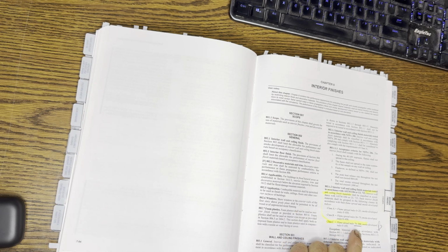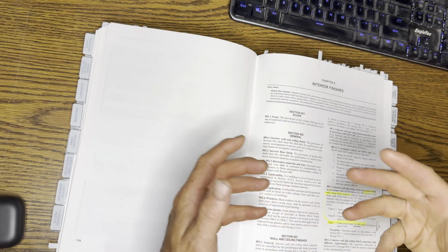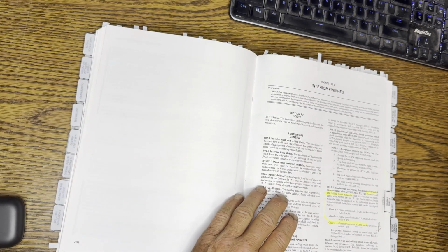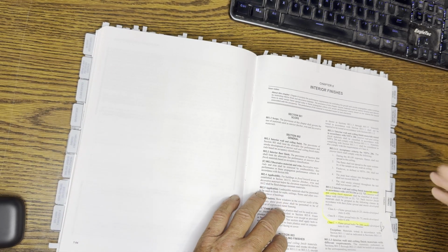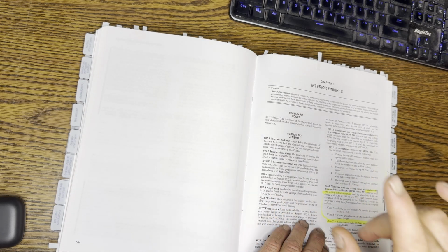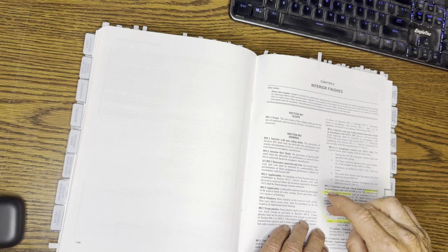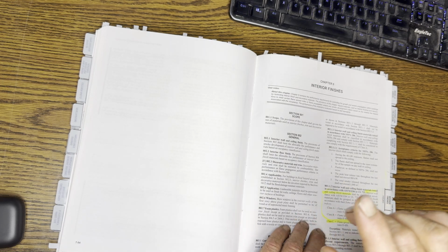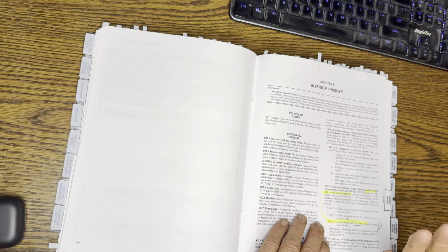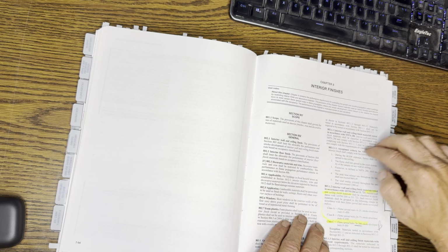And let me explain how this works for ASTM E84. It's the Steiner tunnel test, and what they have is this tunnel, and then they fasten the material on the roof of this tunnel. I don't know how wide it is. It's like 20 feet long, something like that. I'm ballparking. I can't remember exactly what the dimensions were. But they have windows. And what you do is you basically see after a certain duration of time how far the fire has gone under a certain velocity of wind. And concrete is 0, red oak is like 100. And that's what they used as the 2 points to make a scale.